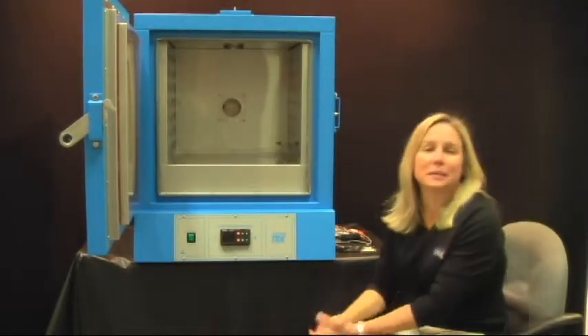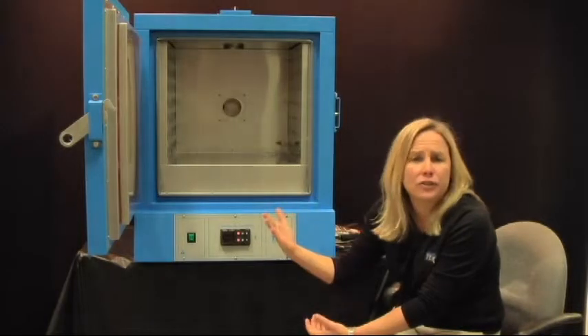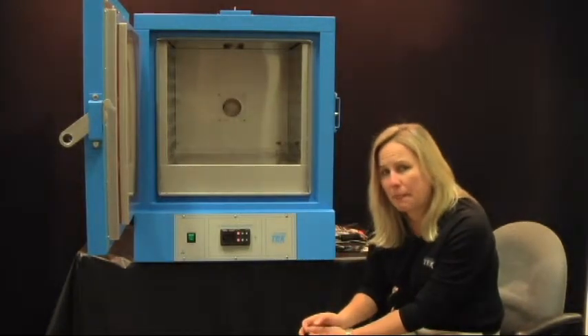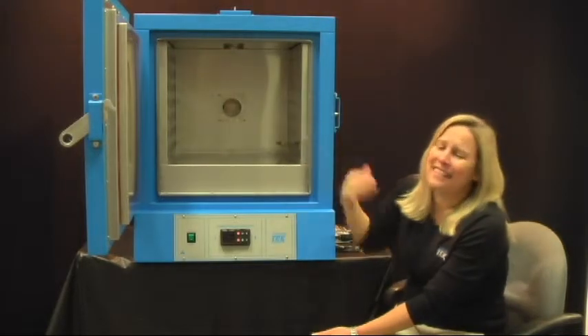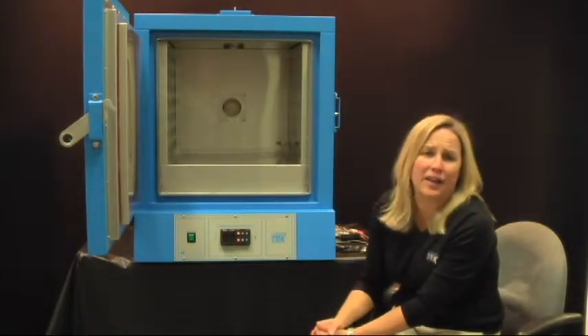Door gasket. Let me say something about the door gasket. The Cascade Tech ovens are generally rated to about 300 degrees C. That's hot. That is hot. And that's beyond hot for most people. They don't need to go that hot.